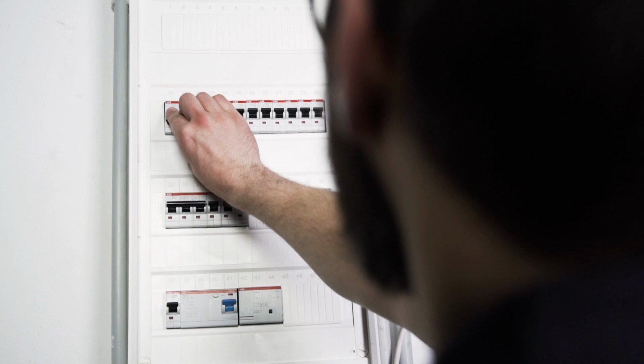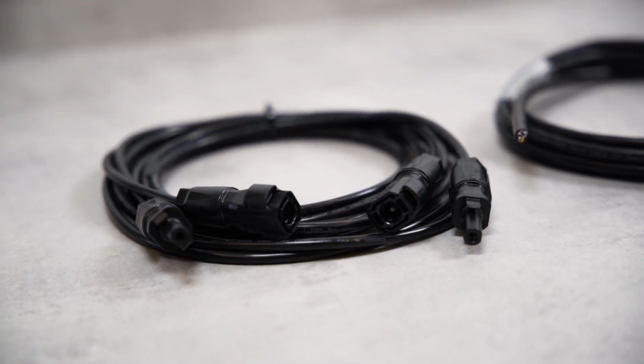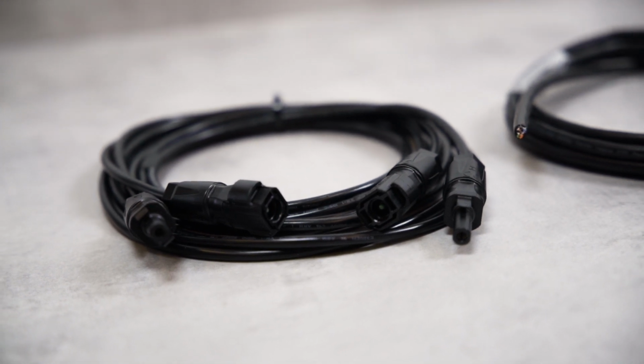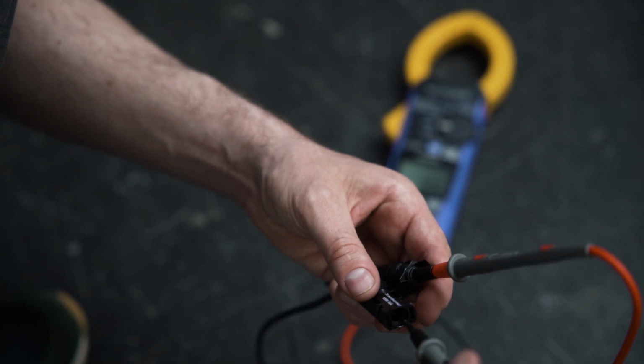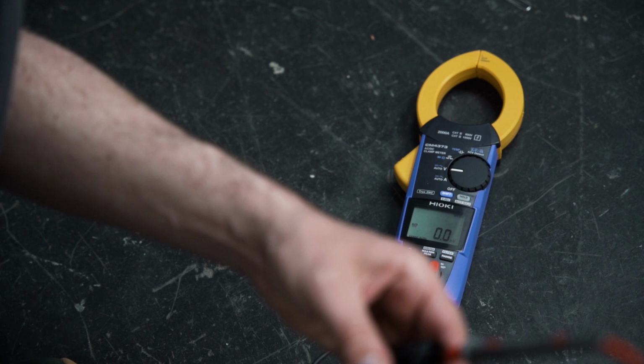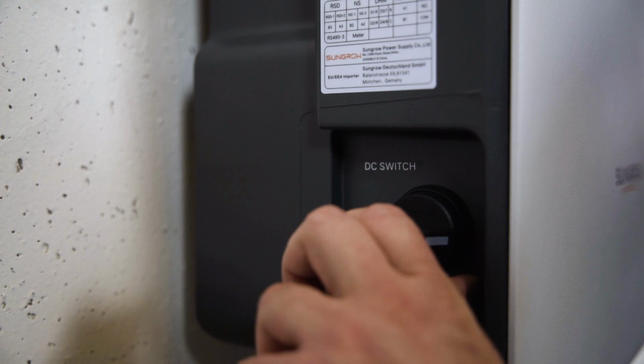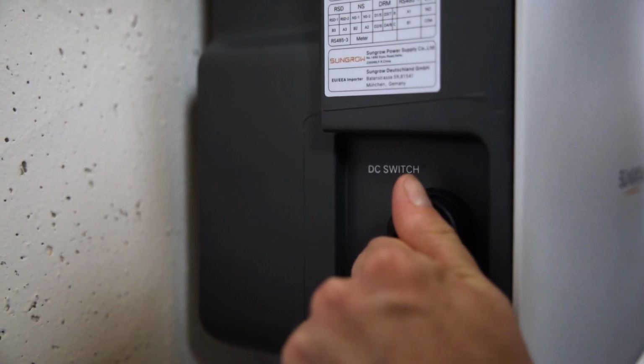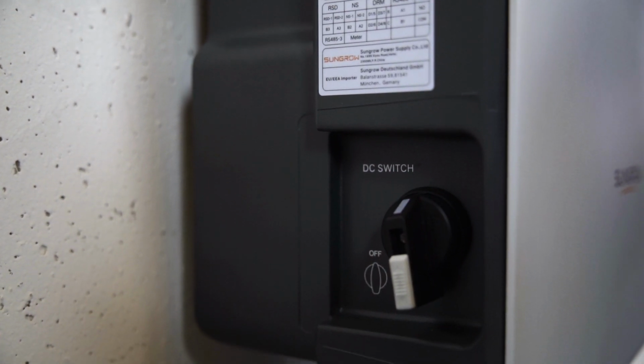Before the inverter can be connected, the AC home circuit breaker must be disconnected, the cables must be de-energized and in perfect condition. Before installation, make sure by measuring that the cables are really voltage-free. You will find all cable requirements and wire sizes necessary for commissioning in our manual. Furthermore, you have to set the DC switch on the left side of the inverter from on to off.